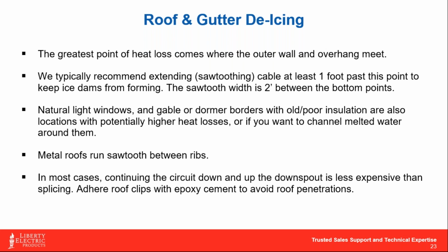When we look at the dollars and cents of continuing a cable run by going down and up a gutter versus putting in a splice kit—a good self-regulating cable splice takes a half hour to 40 minutes. Comparing the labor time to the cost of an extra 12 feet of cable to just go down and back up again, more often than not it's less money for you to get the additional cable and keep the job rolling, rather than risk whether the installer makes a quality splice.